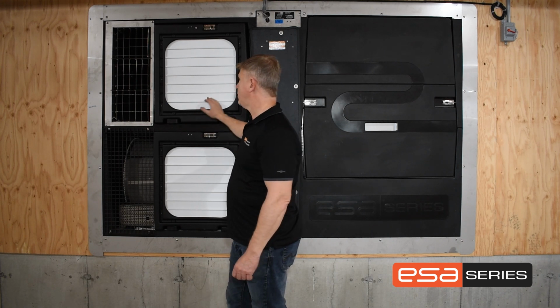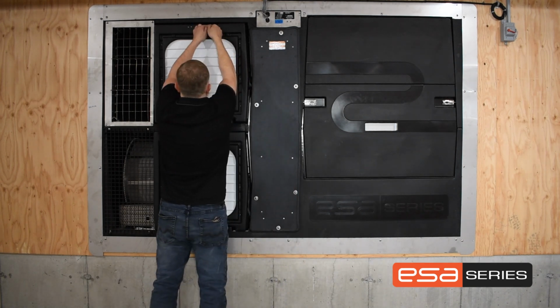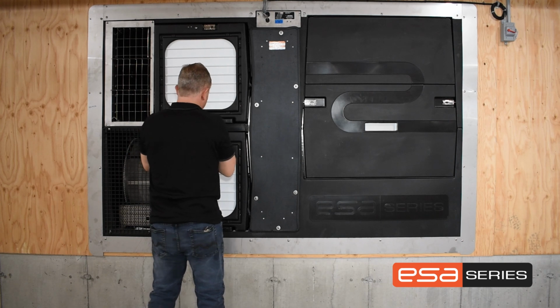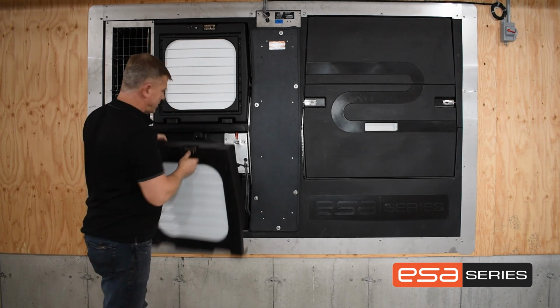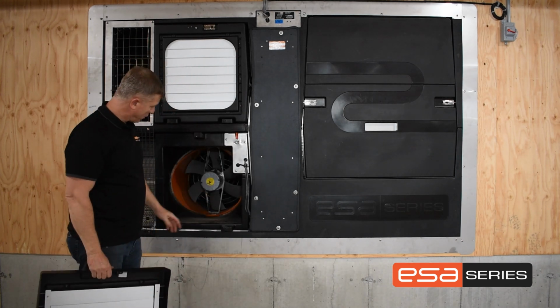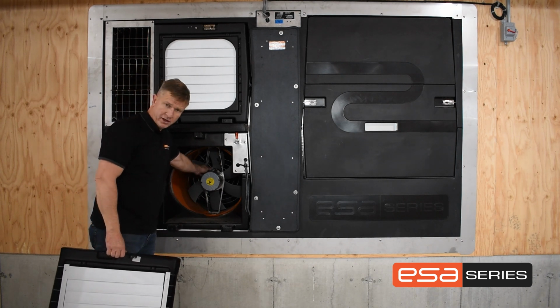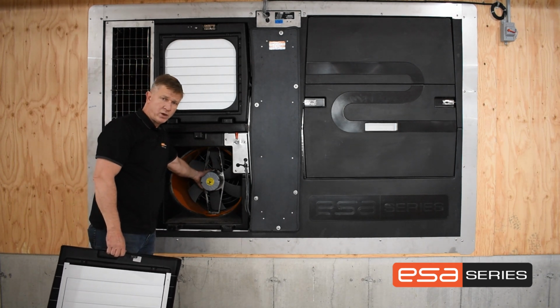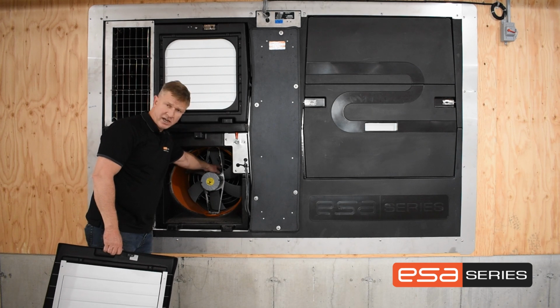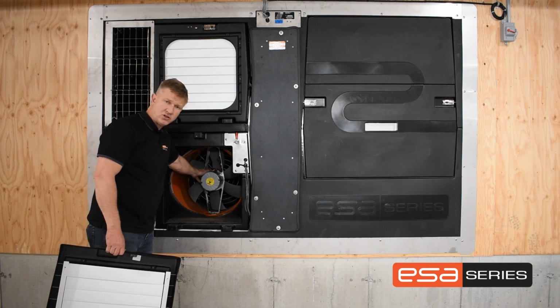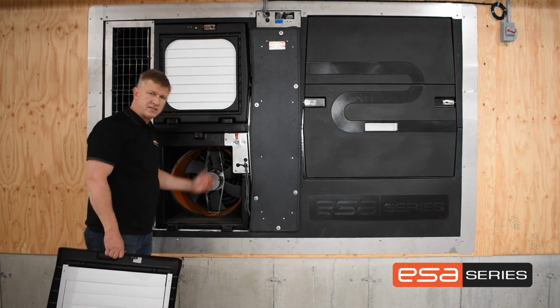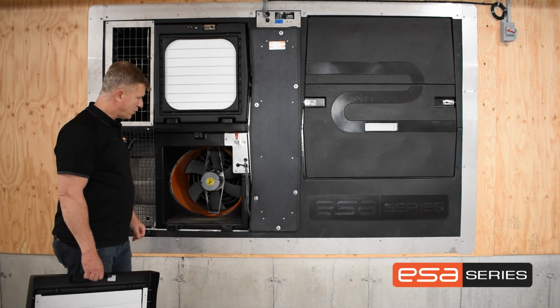Behind here, I'll show you, there's a latch. I'll show you on the lower one. There's a latch here that gives you access to the fan motor. The fan motor has connectors on it, so it's very quick and easy to change. You just disconnect your power clip, and you disconnect your 0 to 10. There are 4 nuts that hold the motor on. Very quick and easy to change.